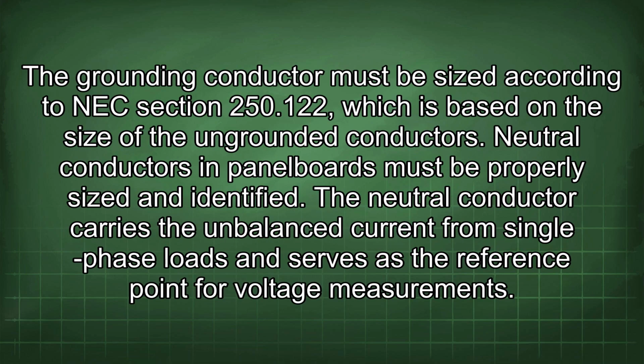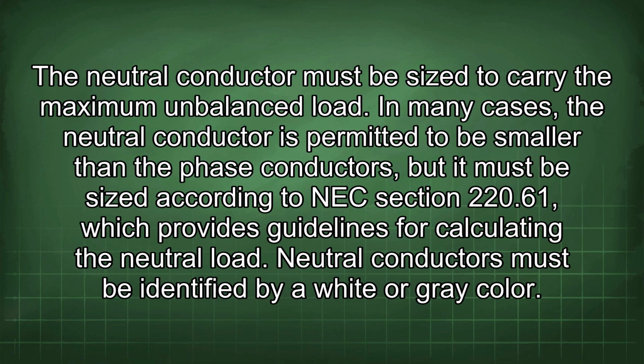The grounding conductor must be sized according to NEC section 250.122, which is based on the size of the ungrounded conductors. Neutral conductors in panel boards must be properly sized and identified. The neutral conductor carries the unbalanced current from single-phase loads and serves as the reference point for voltage measurements. The neutral conductor must be sized to carry the maximum unbalanced load. In many cases, the neutral conductor is permitted to be smaller than the phase conductors, but it must be sized according to NEC section 220.61, which provides guidelines for calculating the neutral load.